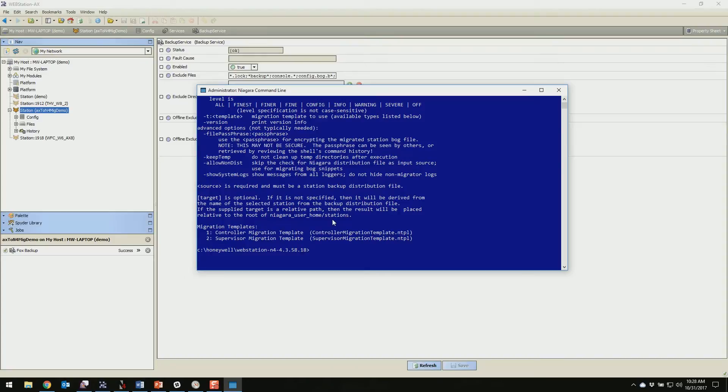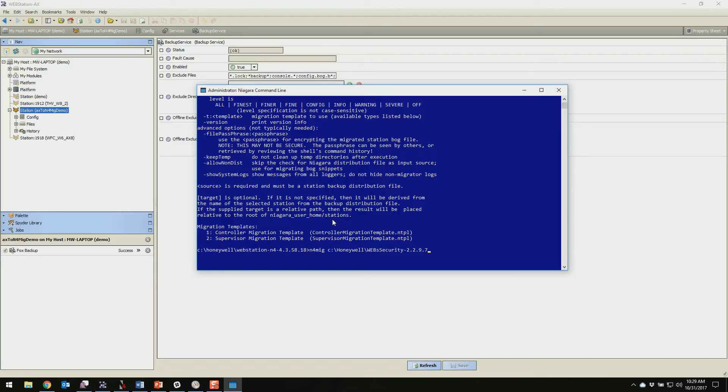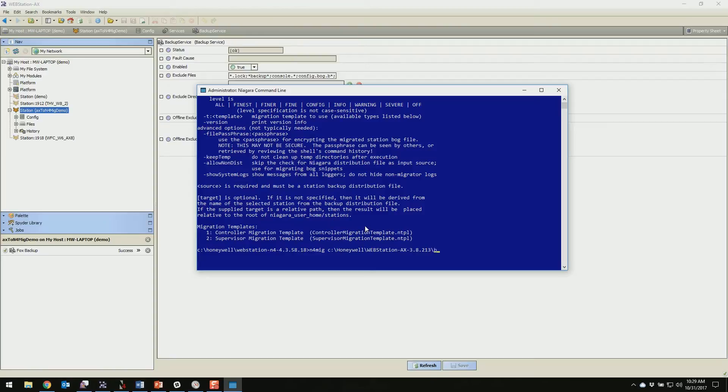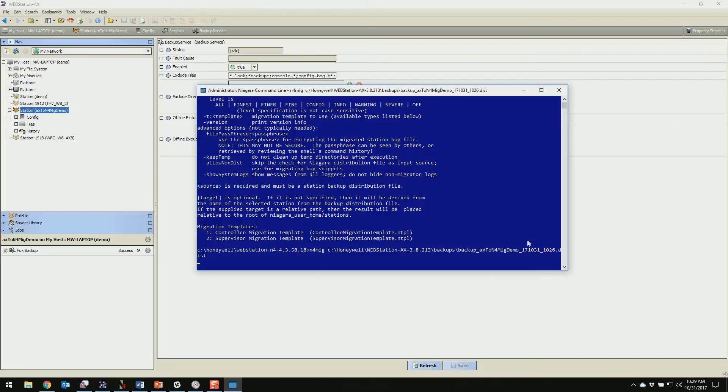But the command itself that we're going to run is n4mig, and then we're going to point the command at our backup that we just made in 3.8. So for me that's going to be c colon slash Honeywell. Now if you're not familiar with the command line you can hit tab on your keyboard and it will auto complete. So I typed in HON and then tab and it auto completed. And then if you just hit tab again it'll keep going through all of your things that fit what you just typed in. So I'm going to tab through here until I get to 3.8.213 which is good, and then I'll go to backups, tab so it auto completes. And then I know my backup starts with backup. So I just typed that in, hit tab, and then this is the correct backup. I'm going to hit enter and that's going to run the command.